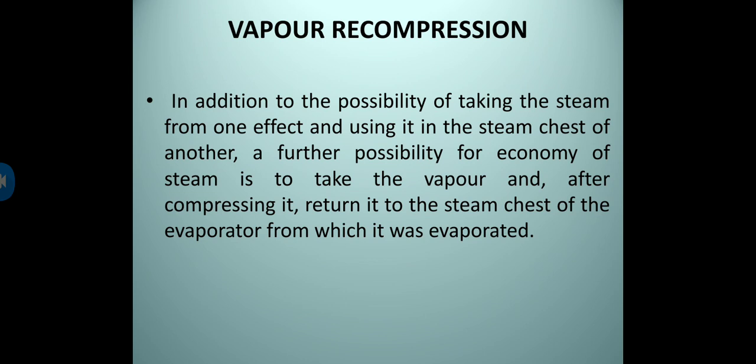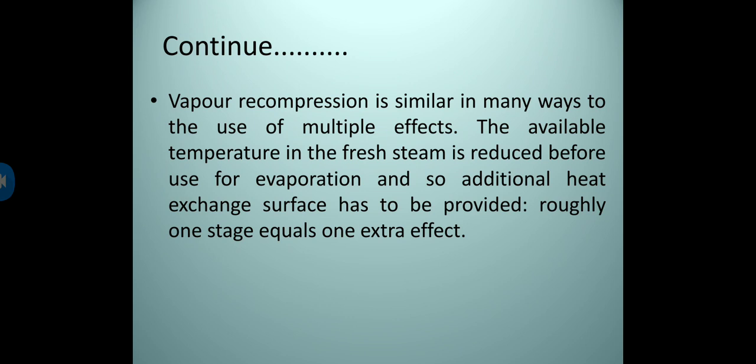The compression can be effected either by using fresh steam at suitable high pressure in a jet or ejector pump, right? Vapor recompression is similar in many ways to the use of multiple effect. The available temperature drop in the fresh steam is reduced before use for evaporation, and so additional heat exchange surface is needed, or we can say that roughly one stage equals one extra effect.